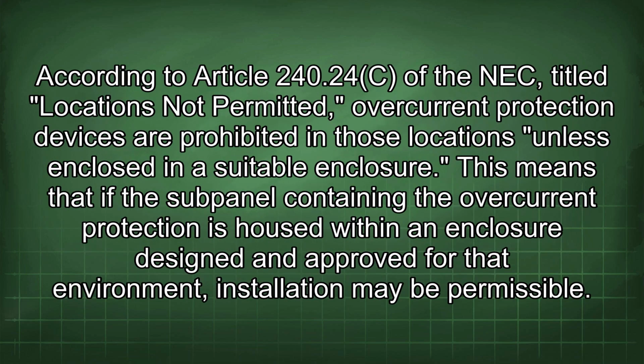According to Article 240.24(C) of the NEC, titled Locations Not Permitted, overcurrent protection devices are prohibited in those locations unless enclosed in a suitable enclosure. This means that if the subpanel containing the overcurrent protection is housed within an enclosure designed and approved for the environment, installation may be permissible.